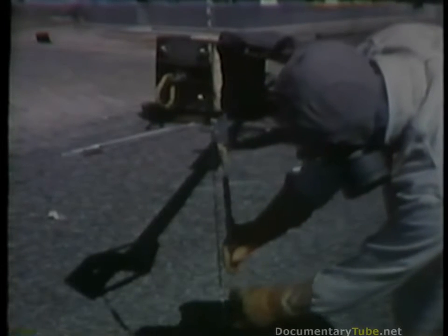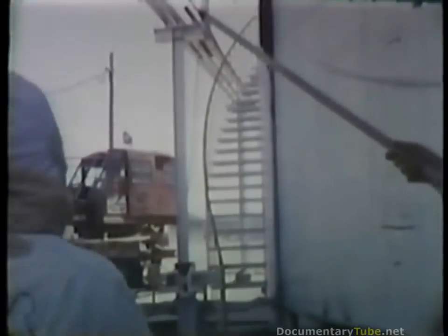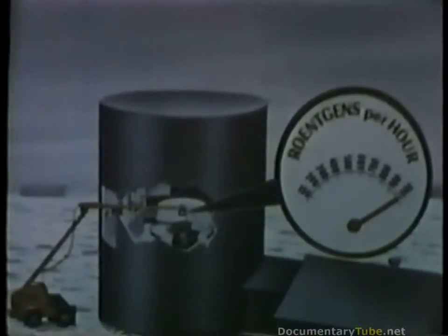Official conclusions eventually confirmed earlier indications that the reactor was nuclearly safe as long as nothing was done to change its unmoderated condition. The air temperature above the reactor head was 47 degrees Fahrenheit. Inside the vessel, about 7 inches above the core, it was 90 degrees Fahrenheit. And at contact, presumably with debris on top of the core, it was 98 degrees Fahrenheit.